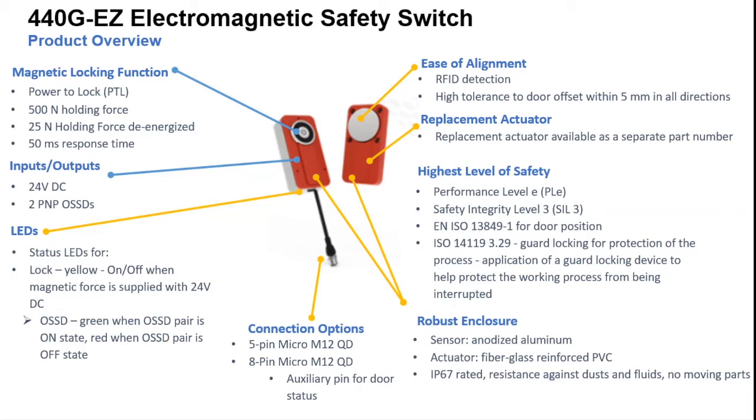It operates at 24V DC with two PNP output signal switching devices. There are LEDs so you can see the statuses for locking on/off and magnetic force supplied. The OSSD is green when the OSSD is in a paired on-state, and red when the OSSD pair is in an off-state. It also has ease of alignment and RFID detection, providing a good tolerance so that if the door starts sagging and is slightly offset, it will still hold without giving a false fault.